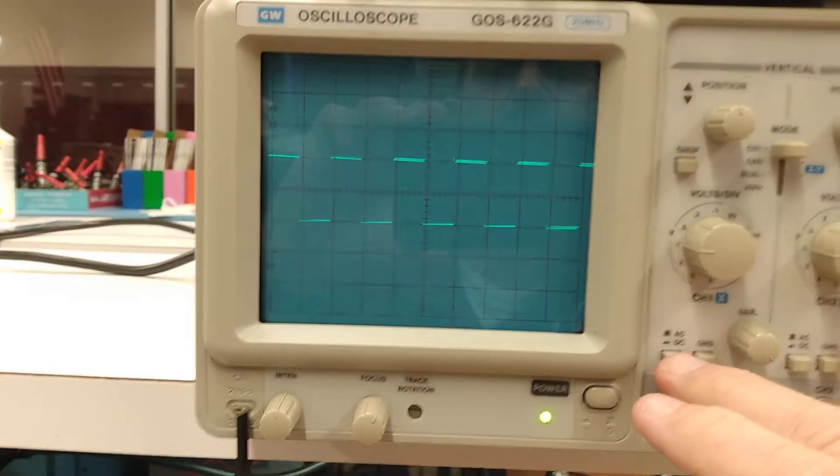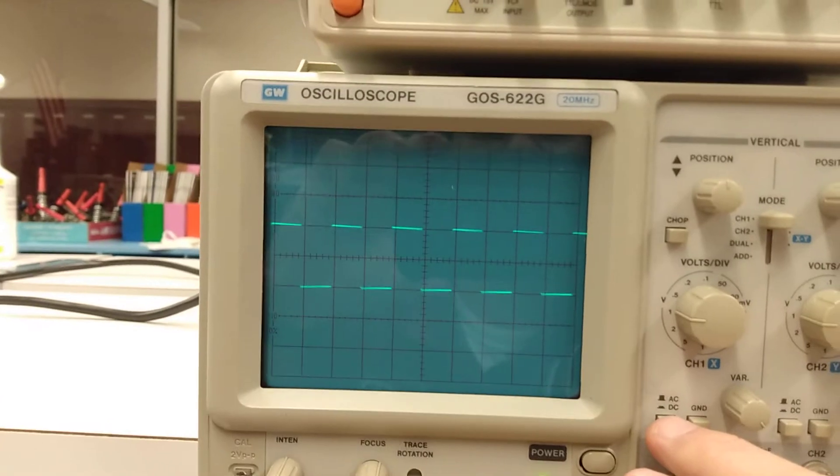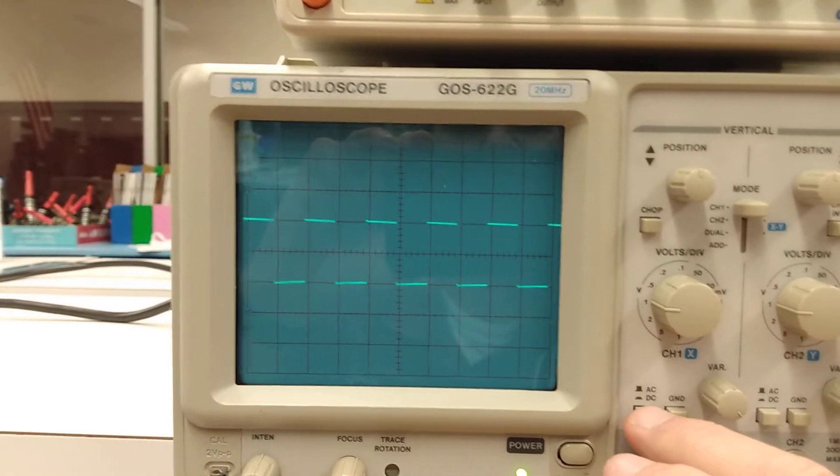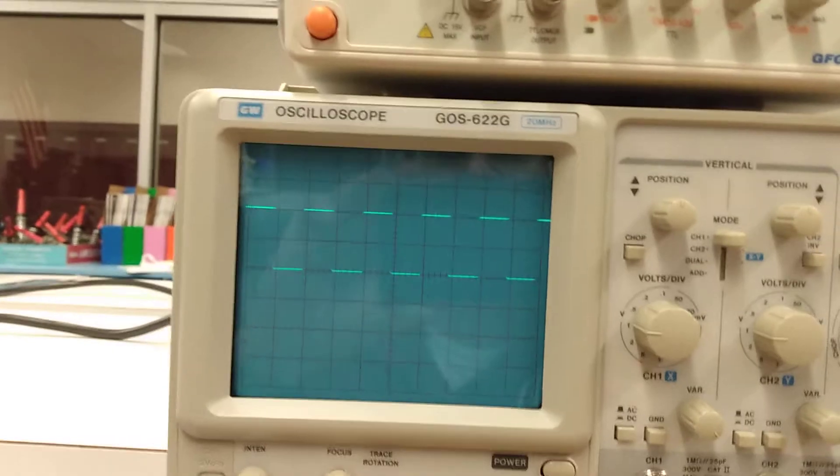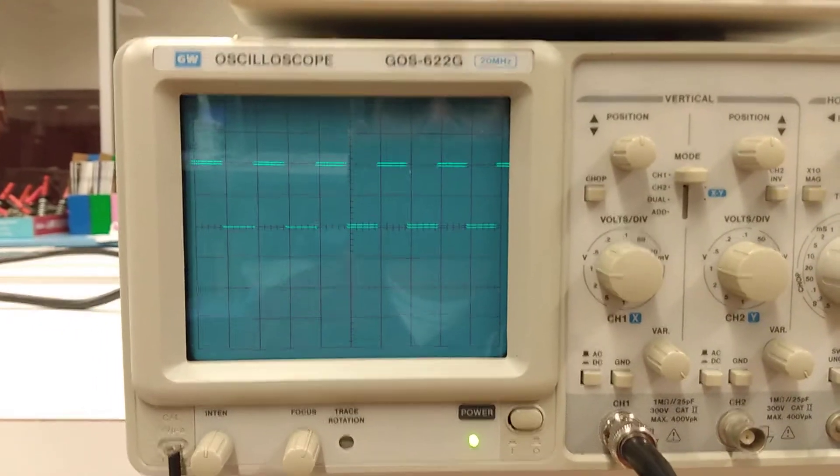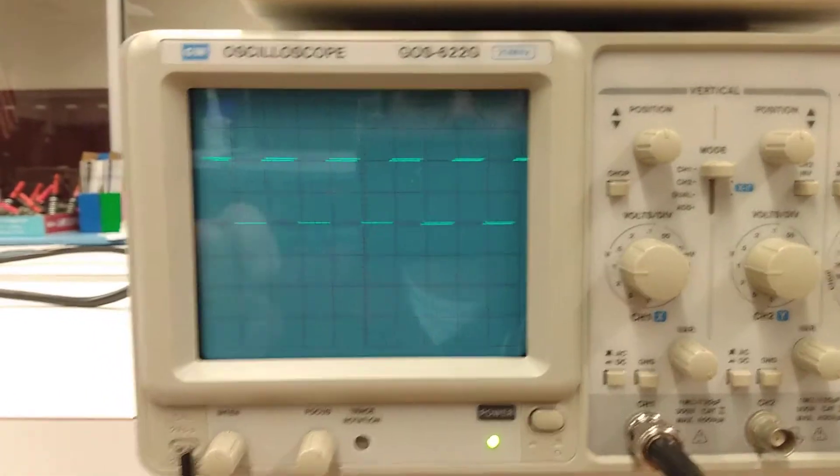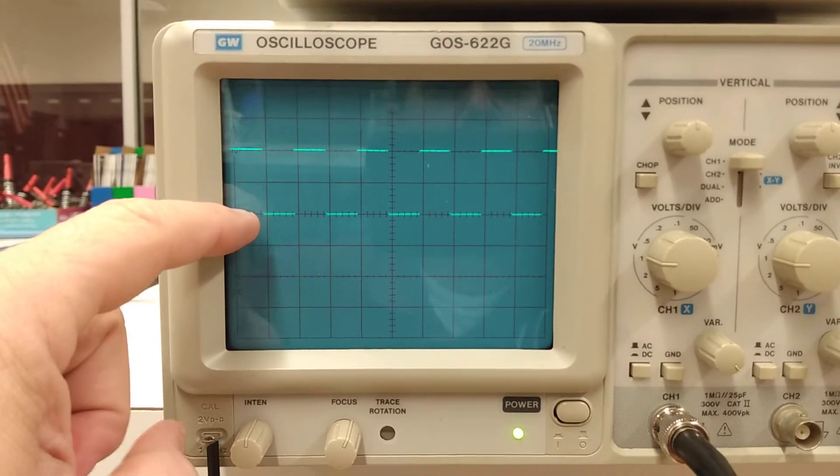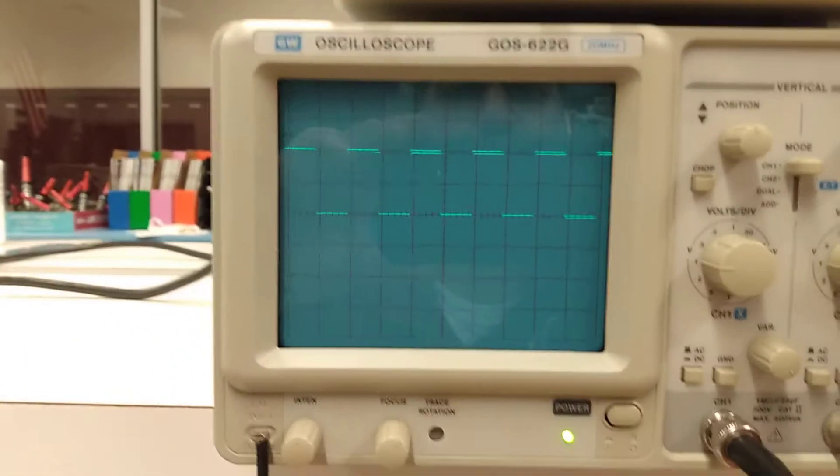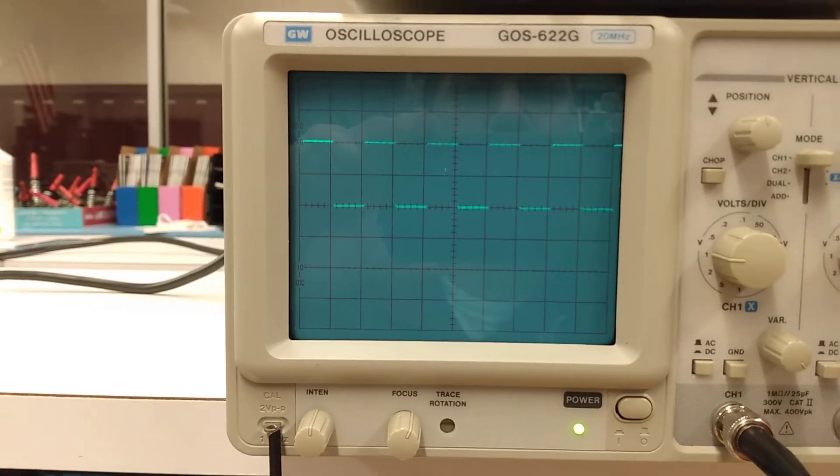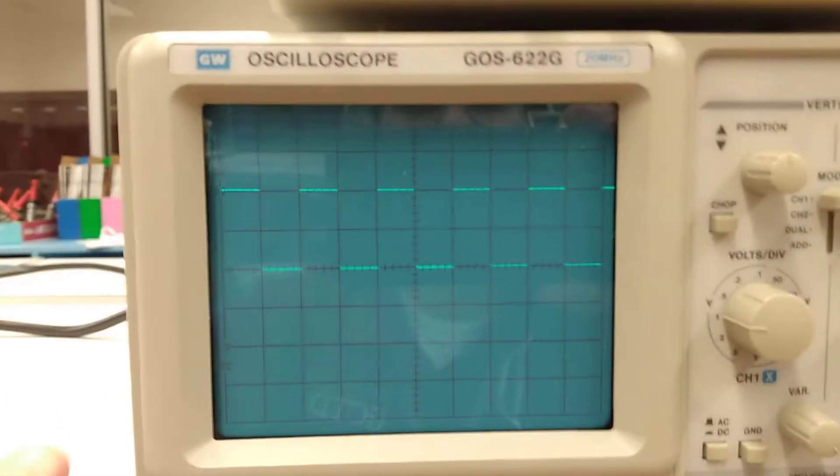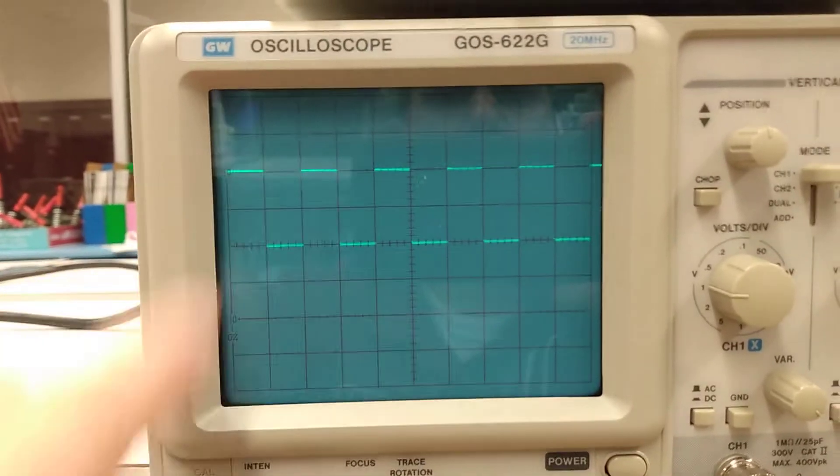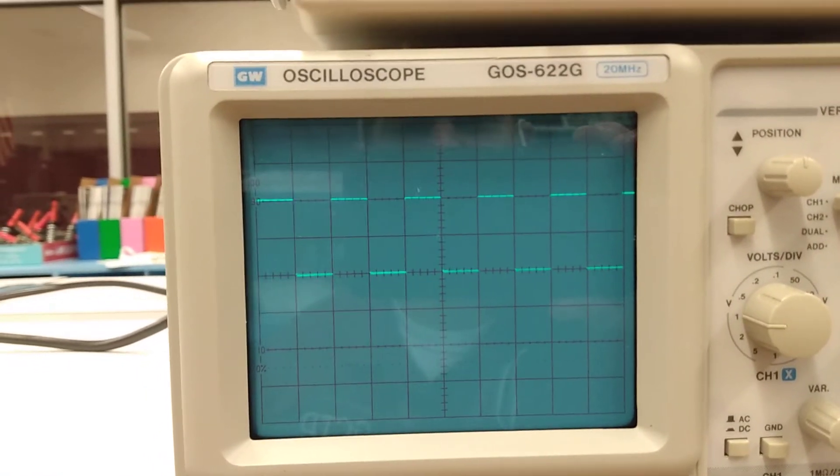Now I did choose a DC offset with this. If I had an AC offset, you're going to see it's down there and there's actually a slight slope to the line. This actually is a DC signal - this is a digital signal, on and off. I have my vertical positioning set so it's on the zero line of my graph here. I might change my horizontal position just ever so slightly so the pickup lines up with the graph or division settings here.